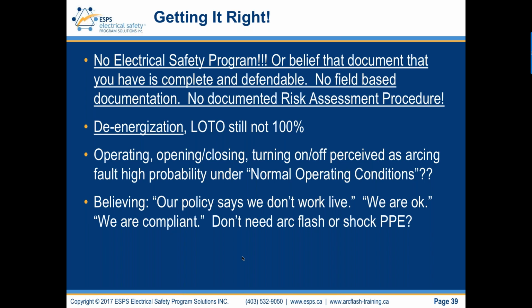There's a misinterpretation or this perception that turning the power off and not testing for zero, which, you know, well, they are testing for zero, but the testing for 0 volts is not energized electrical work. I've talked to large contracting companies specifically, and the CEO goes, Terry, I told all the guys we don't work energized. We're good. And I then asked them, does every electrician own a test instrument, digital multimeter? Oh, yeah. And then they're using it? Well, yeah. Then every electrician in your organization is doing energized electrical work. Voltage measurements for zero or for some value that you're trying to find is energized electrical work.